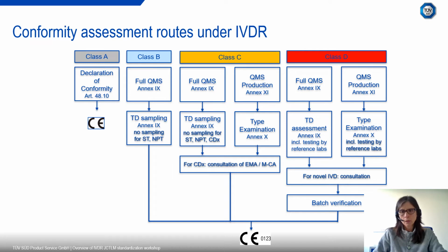The most common route is following Annex 9 of the regulation. This means completing a full quality management system assessment by the notified body through an audit and an assessment of the device technical documentation. This assessment can be done on a sampling basis for class B and C. It has to be done on individual devices, so all devices that are in the scope of the conformity assessment, if the device is class D, or B and C, but for self-testing, near patient testing, or if it's a companion diagnostic.